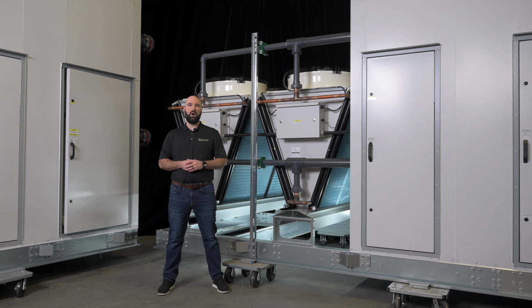We've also got modulating fans on top of it. And so those fans will turn up or down, 0 to 100%, based on the heat rejection need that the system is seeing at any given point. So we don't have 2-speed or single-speed fans banging on and off. It ensures a much quieter operation and a much more reliable circuit temperature, which ensures that our refrigeration circuits can be much more stable and much more reliable.